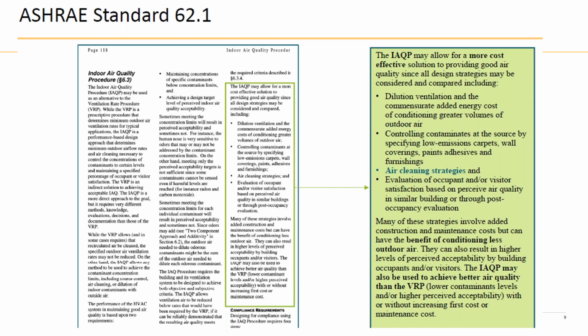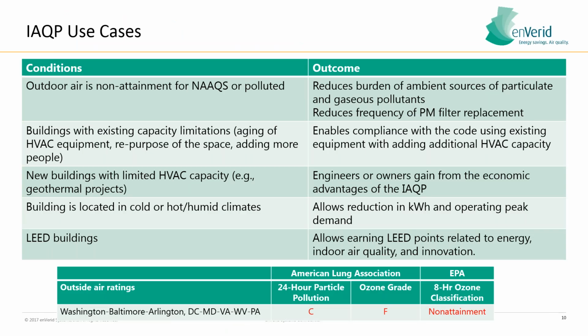Here's the breakout text off to the right. You can see that air cleaning strategies are used within the indoor air quality procedure within ASHRAE 62.1. An interesting note in the bottom right-hand corner says the indoor air quality procedure may also be used to achieve better air quality than the ventilation rate procedure. And we see this frequently in metropolitan areas. For example, I'm based out of Washington, D.C.